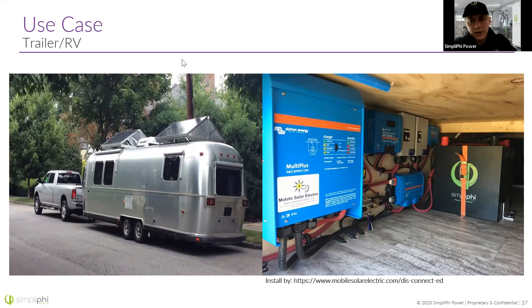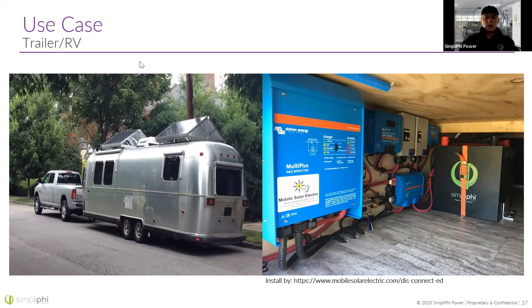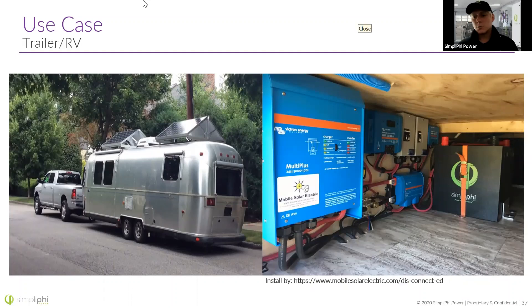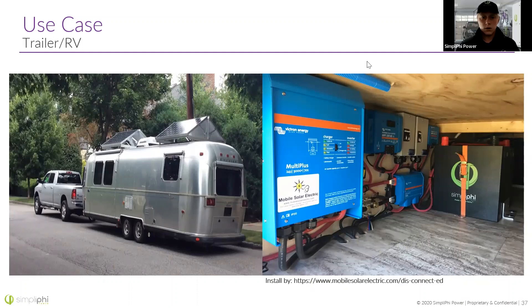They are eligible for SGIP, but that is more of a residential rebate program. As for the range of temperatures lithium ion batteries can withstand inside a cabinet: lithium batteries cannot charge below freezing, but they can operate from negative 4 degrees Fahrenheit all the way to 140 degrees Fahrenheit — that's the range for storage or discharge. Thanks everybody, have a good one!